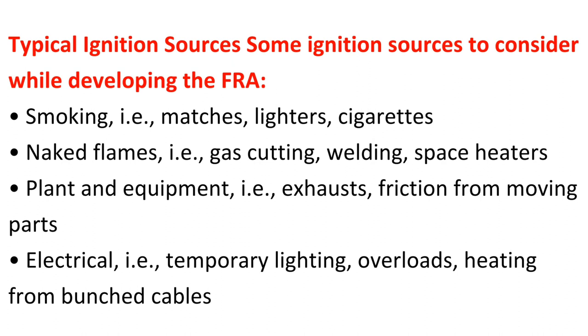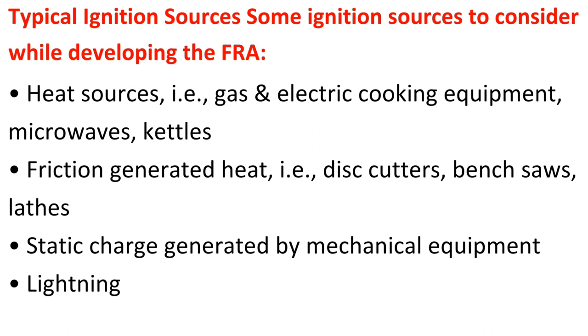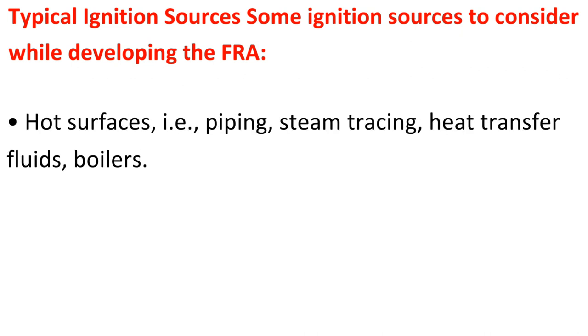Electrical sources, that is, temporary lighting, overloads, and heating from bunched cables. Heat sources, that is, gas and electric cooking equipment, microwaves, and kettles. Friction generated heat, that is, disc cutters, bench saws, and lathes. Static charge generated by mechanical equipment. Lightning. Hot surfaces, that is, piping, steam tracing, heat transfer fluids, and boilers.